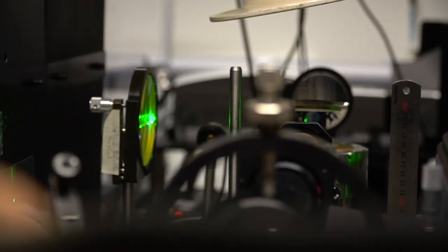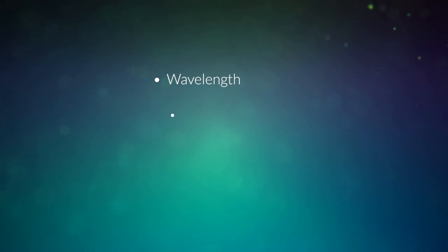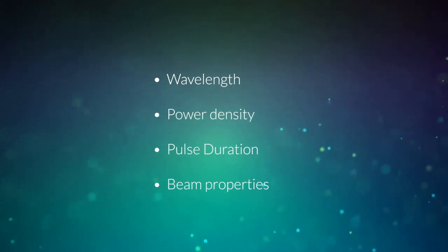To protect the eye when working with lasers, specific eye protection may need to be worn. The type of protective eyewear will depend on the wavelength, power, pulse duration, and beam properties of the particular laser that you are using. And a safety assessment of the experiment and laser system must be performed to identify what level of protection is required for each activity.